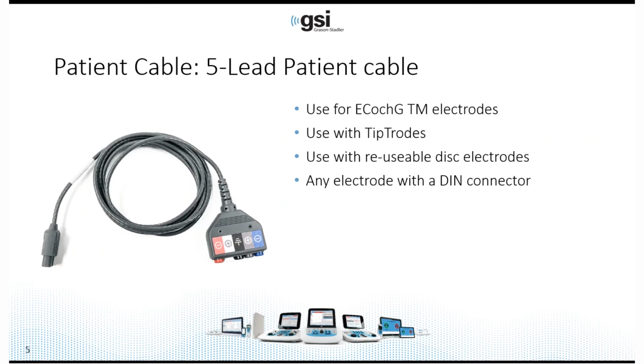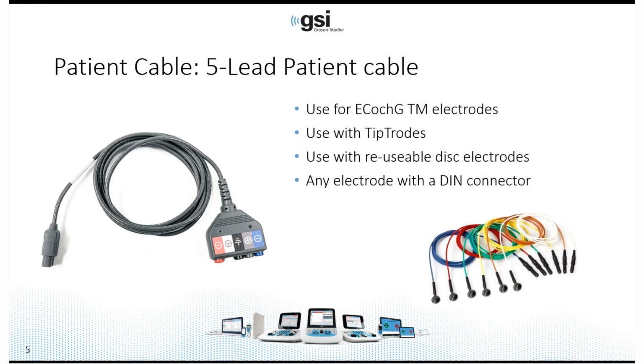We also provide a 5-lead patient cable that would have to be used if you were using the TM electrode for ECochG or using Tiptrodes or any reusable disc electrode. So if you prefer to use the reusable electrodes, this would be the patient cable that you would use for all your tests. Any electrode that ends in a DIN connector, you would have to use the 5-lead patient cable. Every test type included with the Audera Pro can be completed with this cable.